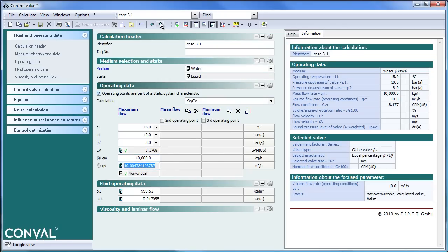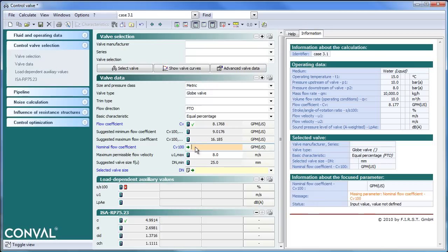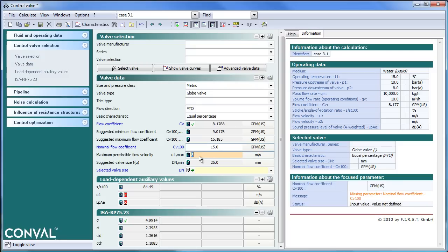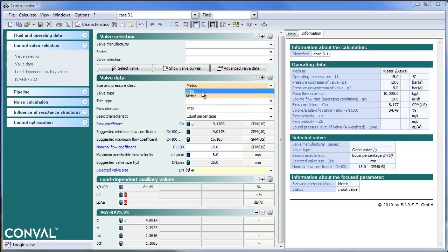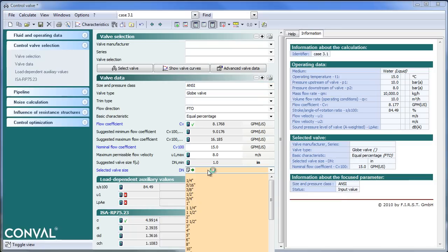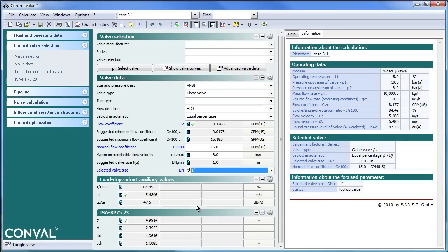On the next page we will actually select the nominal flow coefficient. We get an advice between 9 and 16. I'll take 15. And I need to come up with a size. I will take an ANSI unit and I will select the one inch which is the recommended.